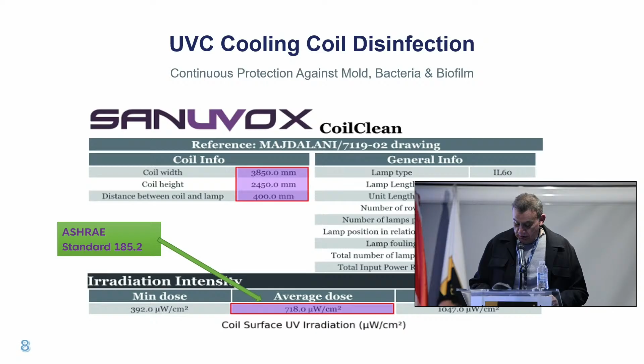One thing here also, in the cross-section of the installation, you see something called the reflector. We need to have a reflector behind the light, either stainless steel or something that's really shiny, to reflect the entire light beam towards the coil and not anywhere else. So the reflector is an integral part of the installation.